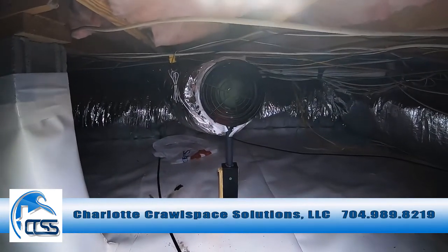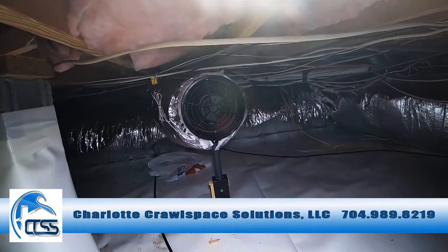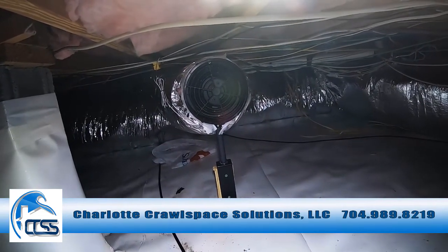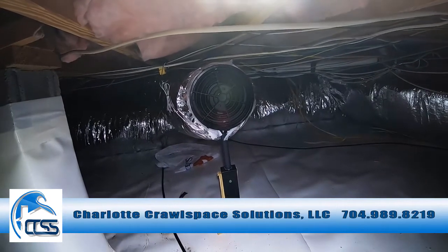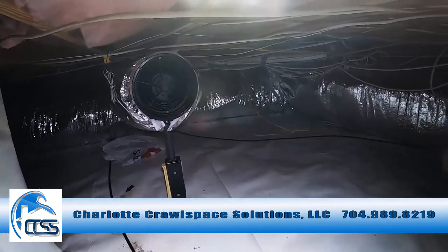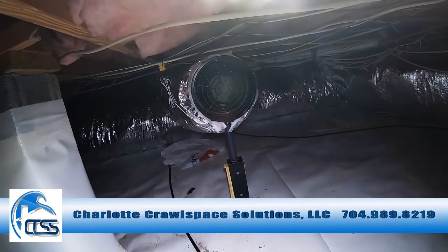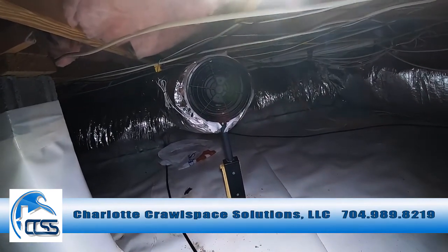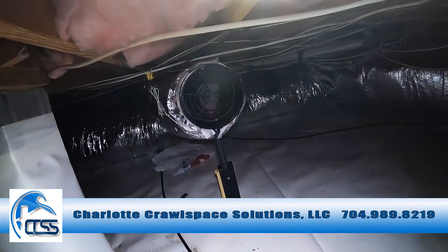This is what we call a pipe fan. This pipe fan is hooked up to a 25-foot 8-inch duct kit, and this is how we're moving the air from one side of the crawl space to the other side — which the other installer failed to design into the original program. There are two of these pipe fans, one about 20 feet to my right. We had to carefully weave the duct kit through this labyrinth of duct work to get the conditioned air from either the intakes on the left side of the house or the dehumidifier and move that conditioned air to where there was a difference in wood moisture on each side of the crawl.